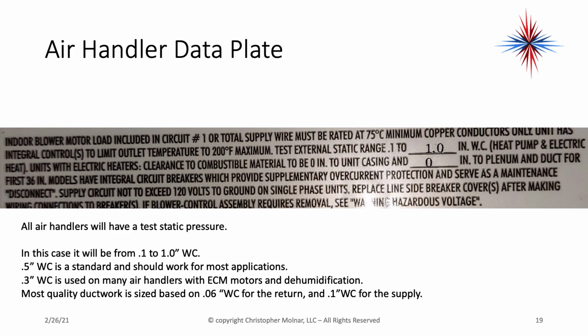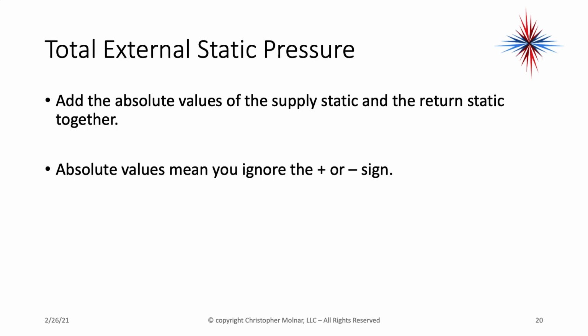So again, look at the data plate to find out what our maximum static pressures are. And you shouldn't be at the max. Again, things do not get better with age. Add the absolute values of the supply static and the return static together. Absolute values mean you ignore the positive or negative sign.